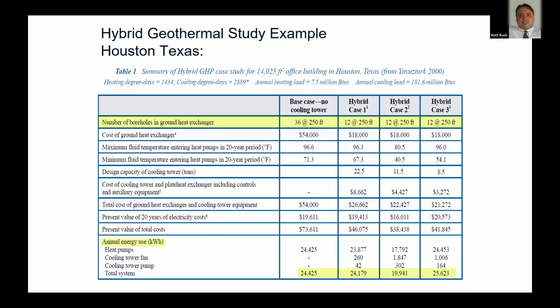With that well field cost in the $18 to $20 a bore foot range, it may be a little higher now with market conditions. It's a significant cost advantage, and often more efficient to operate because you're not pushing the limits of that well field, especially in cooling dominant applications where that temperature tends to creep up over time in the summer months. So just something to think about.